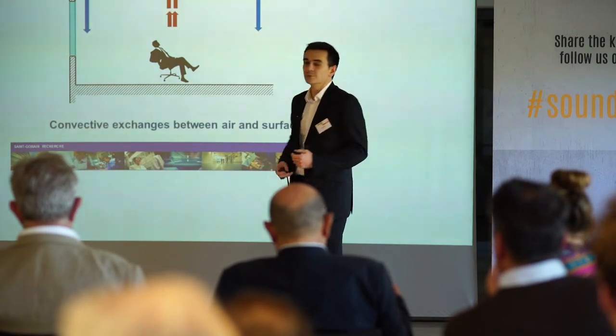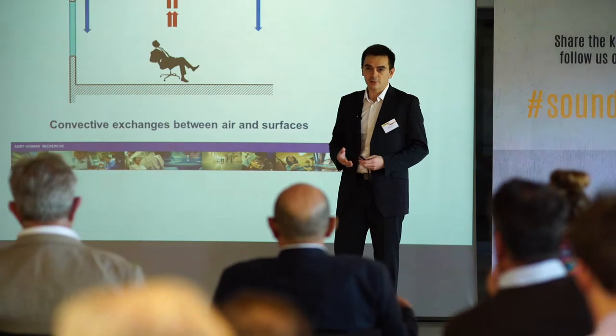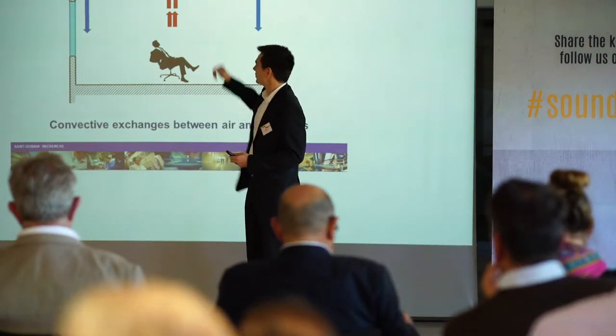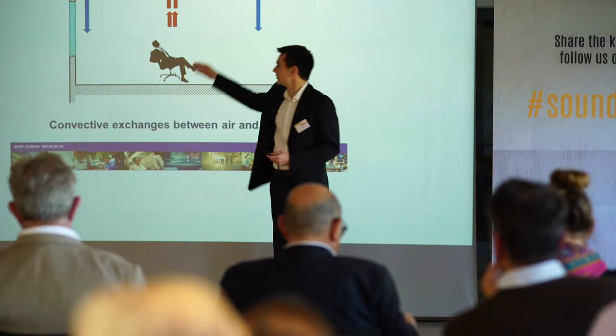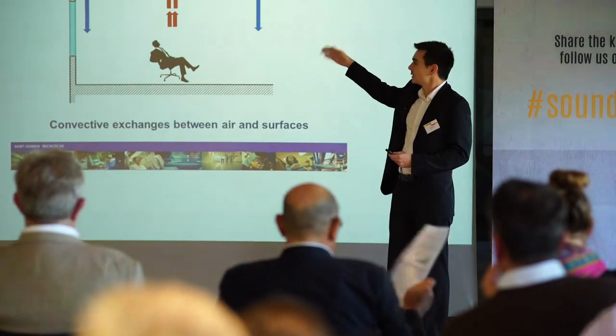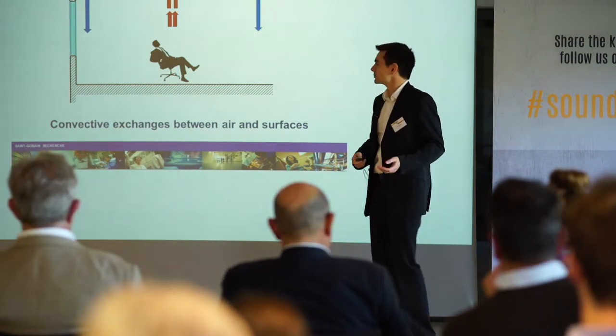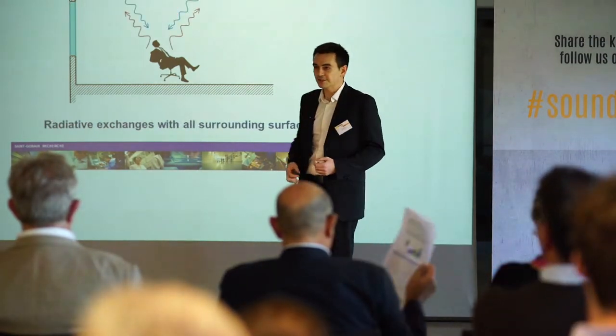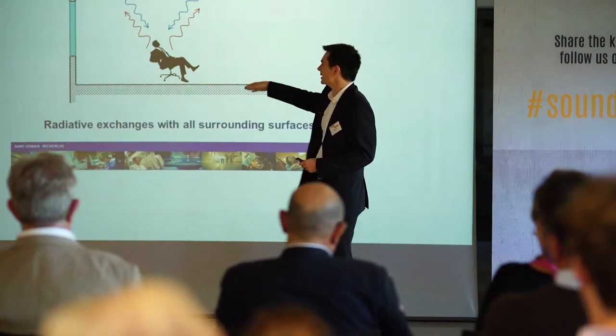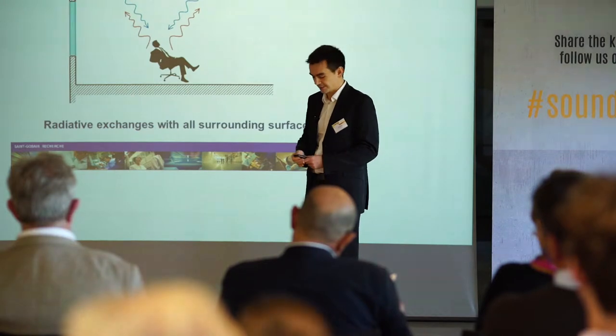During the day, due to the activity, the temperature of the air will rise, and due to convective exchange, the air will climb and exchange with the cooled ceiling. The ceiling will cool the air and improve the thermal comfort. Of course, we also have some radiative exchange. During the day, the occupant will exchange with the cooled ceiling, but also with all the other surfaces.